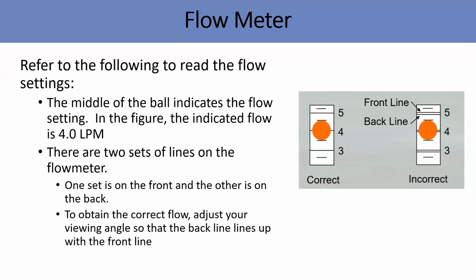So for the flowmeter setting, you have to refer: when you set 4, it should be at the middle point. At the same time, if you want to know whether your flow is good or not, this particular reading has to be stable. The ball should stay in one place properly. You shouldn't see it go up and down. That means the reading is good actually. That means there's no pressure issue, low pressure or high pressure. At the same time, it indicates the flow is good.